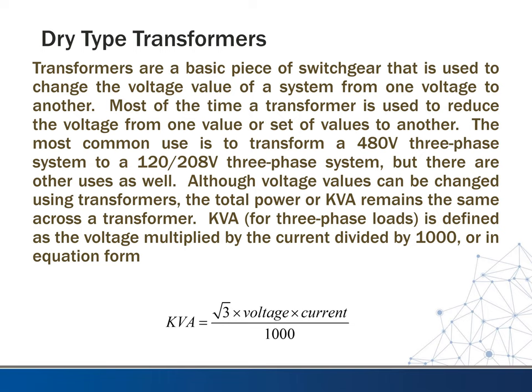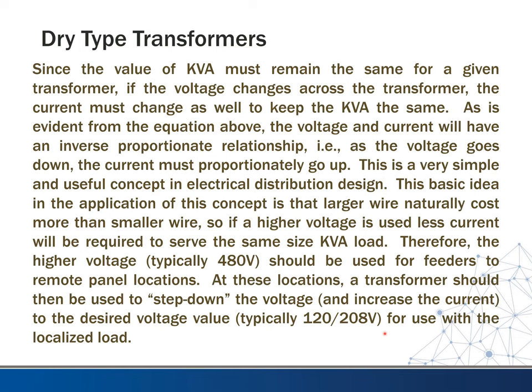Although voltage values can be changed using transformers, the total power, or KVA, remains the same across the transformer minus some minor losses. So remember, the KVA for three-phase loads is defined as the voltage multiplied by the current divided by 1,000, or in equation form, it looks like this right here. KVA equals square root of 3, voltage times current over 1,000. Since the value of KVA must remain the same for a given transformer, if the voltage changes across the transformer, the current must change as well to keep the KVA the same.